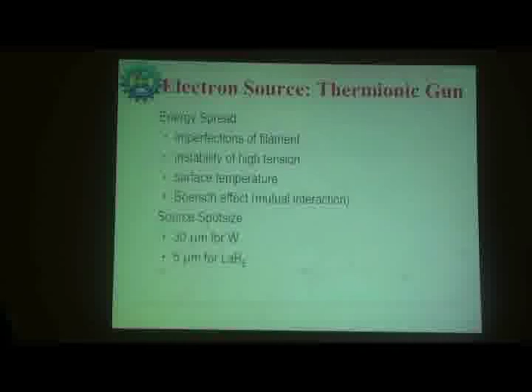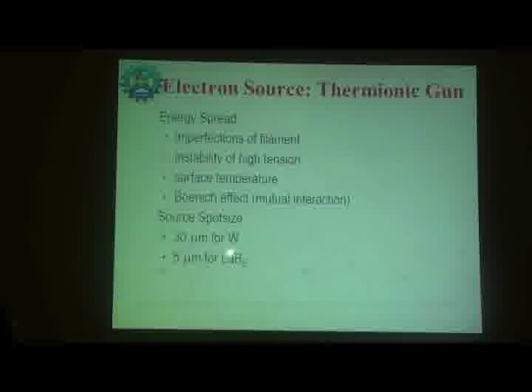So mostly it is the source spot size that decides this. With tungsten you can get a source size of something like 30 micrometers. With LaB6 you get 5 micrometers. So these are the deciding factors. Suppose you have LaB6, you can get a much smaller spot size, and you can go for very high resolution.